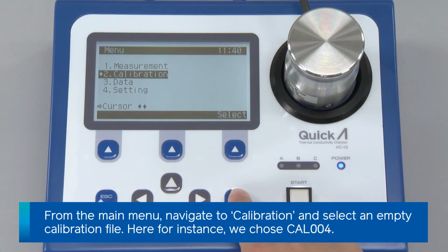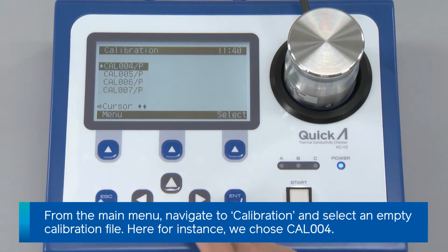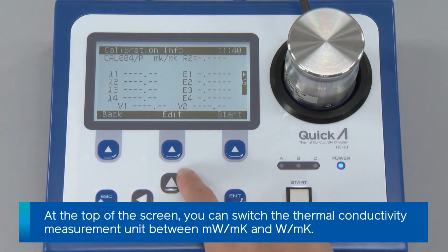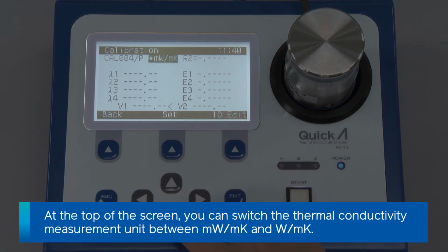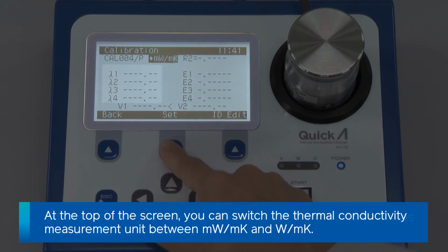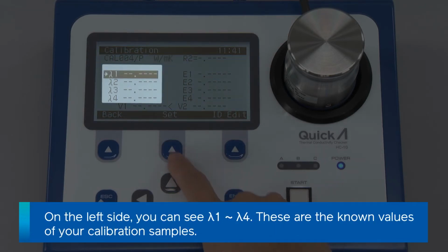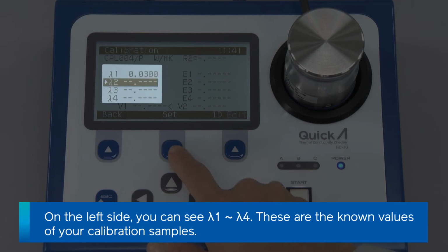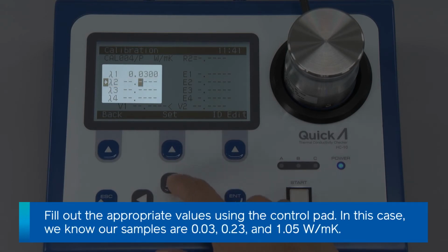From the main menu, navigate to Calibration and select an empty calibration file. Here, for instance, we chose Cal004. At the top of the screen, you can switch the thermal conductivity unit between milliwatt per meter Kelvin and watt per meter Kelvin. On the left side of the screen, you can see the lambda values, lambda 1 to lambda 4. These are the known values of your calibration samples. Start filling the values in order using the control pad. In this case, we know our samples are 0.03, 0.23, and 1.05 watt per meter Kelvin.